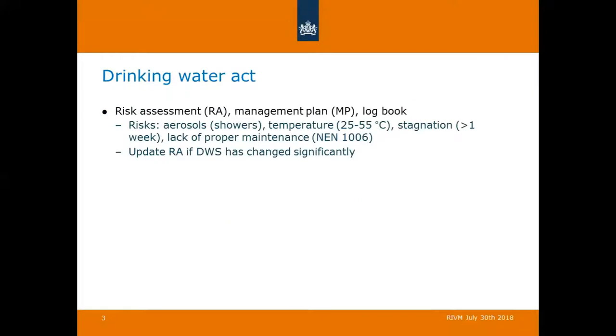First, the Drinking Water Act. The legal owners of the drinking water system have to make a risk assessment, a management plan, and record all their actions in a logbook. They have to assess the risk if there are any aerosols present, for example in showers, whether there's any risk with temperature between 25 and 55 degrees Celsius, whether there's any stagnation for more than 1 week, and also whether there's a lack of proper maintenance, for example dead legs or showers that are not used anymore.